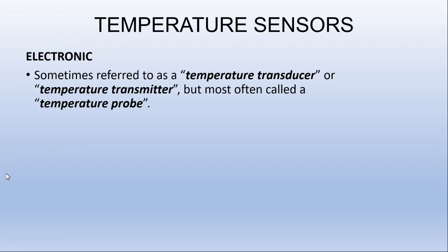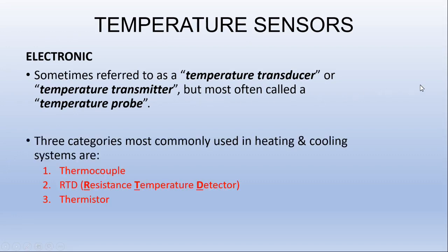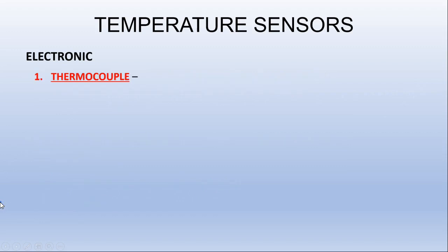Okay, electronic. Electronic temperature sensors are sometimes referred to as a temperature transducer, a temperature transmitter, but most often called a temperature probe. Three categories most commonly used in heating and cooling systems are the thermocouple, an RTD, which stands for resistance temperature detector, and a thermistor. First, we'll talk about a thermocouple.